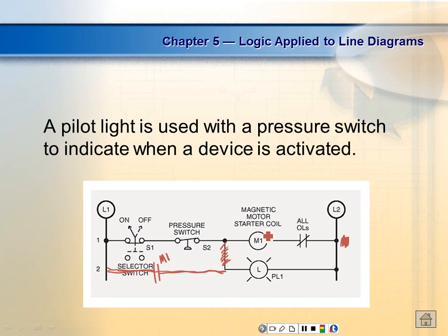And what we got used to is dropping the new one on the side and pulling one wire off at a time and doing what? Moving it to the same spot on the other relay. That way you wouldn't even have to worry about documenting. But yeah, the advantage of doing it this way is that if your relay coil burns up in this light right here, the light will go out. The other way, the relay coil will burn up and the light will still come on. So a lot of people would assume that this right here was burned. That's what got me one time. Really?